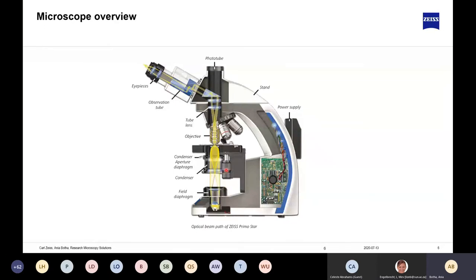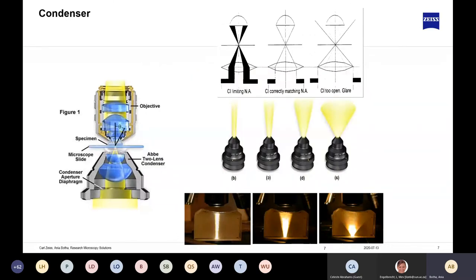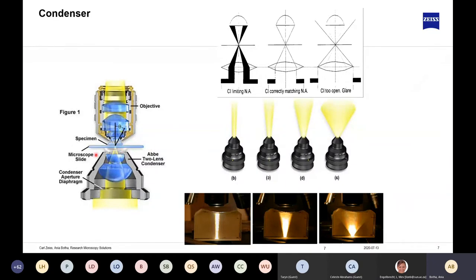Moving up one step to the condenser: the function of the condenser, as the name suggests, is to condense the light and bring it together to form a pinpoint just underneath your sample. The light then refracts and goes into the objective.